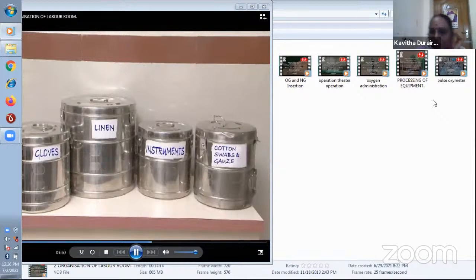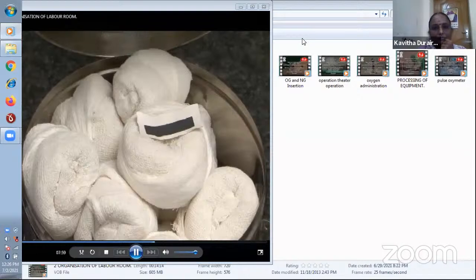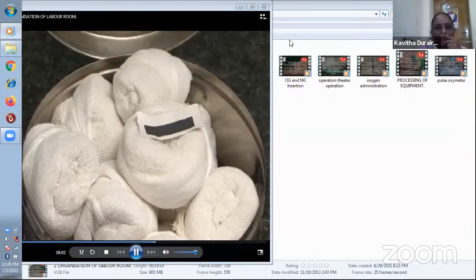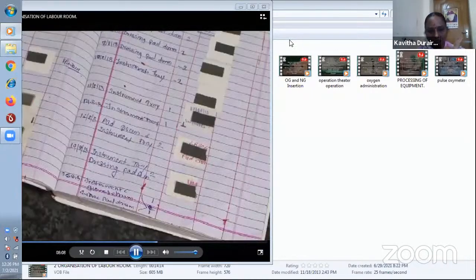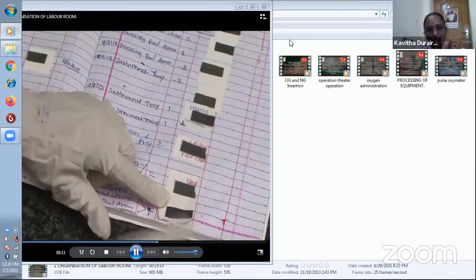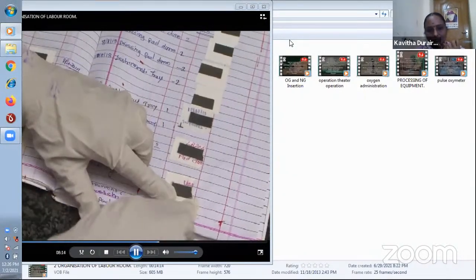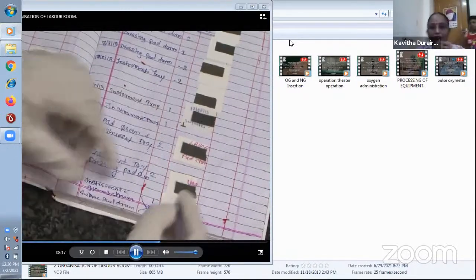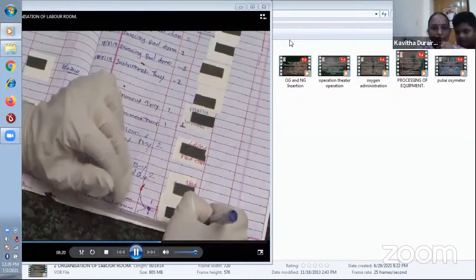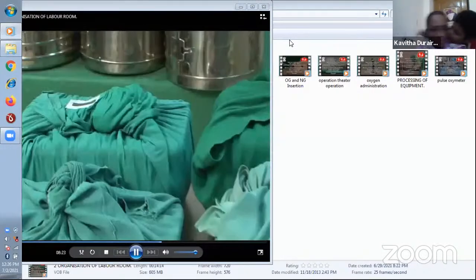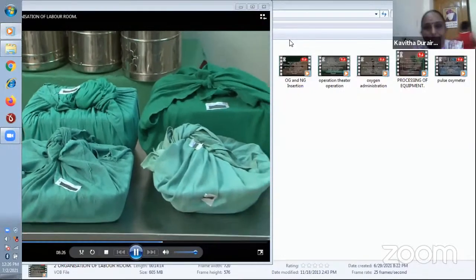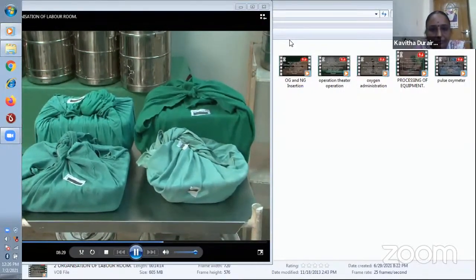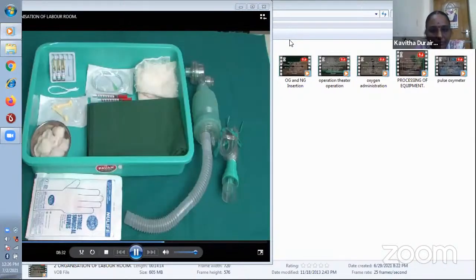Drums containing sterilized items like gloves, linen, instruments, cotton swabs, and gauze pieces. When you open the autoclave drum, confirm that the color of the strip inside the drum and on the wrapped sets has changed. Remove the strip and place it in the register. If there is no color change, the items have not been properly sterilized and the drum needs to be sent for autoclaving again. Each delivery tray should have pre-autoclaved and wrapped instruments in enough numbers so that one set is available for each delivery.